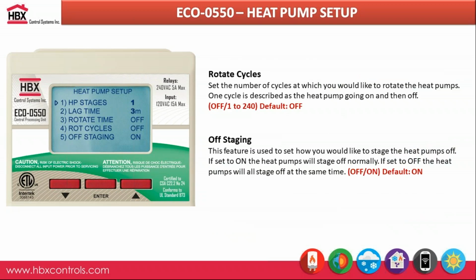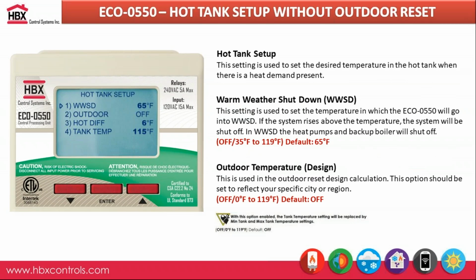You can also do them off of cycles. So again, a heat pump firing on and off is considered 1 cycle. And again, you can adjust those from 1 to 240 cycles based off rotating your heat pumps on there. Depending on how you want your heat pumps to shut off, you can have them set to on, which will just shut off based on the lag time that you have set to turn on those heat pumps. If you were to set those off, your heat pumps will just shut off all at the same time. So you have 2 different options of how you want those heat pumps to shut off on there.